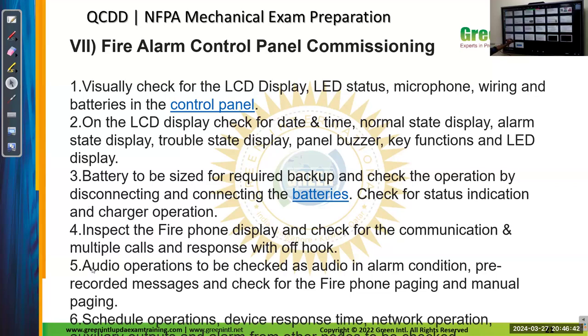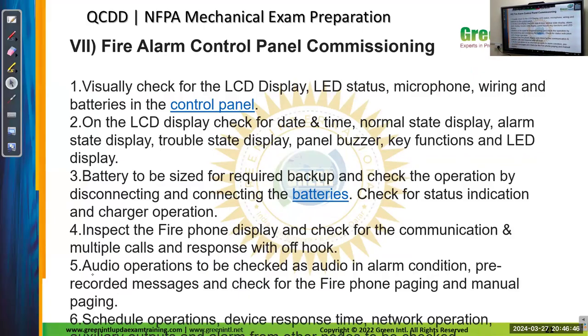Audible operations to be checked as audio in the alarm condition, pre-recorded messages, and check if the fire phone is paging and manual paging. So this is how the integrated testing will work.